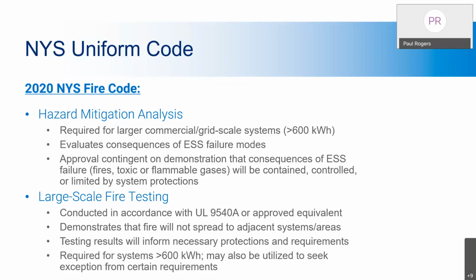Getting back into large scale testing, the uniform code did put in large scale fire testing, adopting 9540A as the standard, or an approved equivalent. So if the AHJ or code official has some test equivalent to 9540A and it's approved by the authority having jurisdiction, they can adopt that and say, yeah, we're going to approve this testing and allow the installation based on testing outside of 9540A. I haven't seen it done yet, but that provision is in the code. That came about because at that time UL was still ironing out some issues with 9540A, and they did a great job making sure they ironed that out.